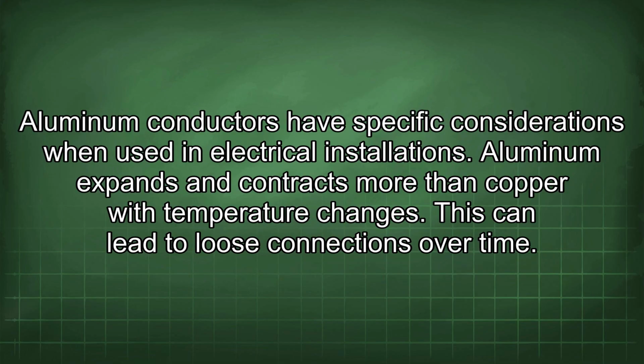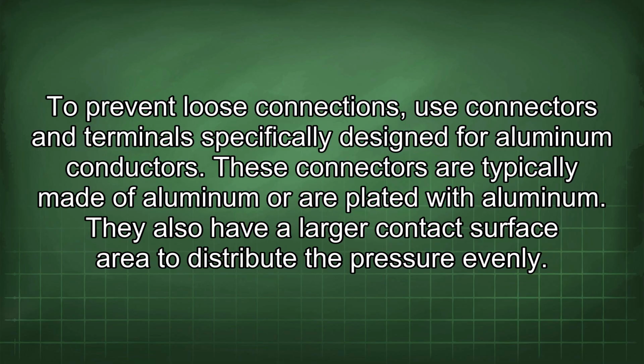Aluminum conductors have specific considerations when used in electrical installations. Aluminum expands and contracts more than copper with temperature changes. This can lead to loose connections over time. To prevent loose connections, use connectors and terminals specifically designed for aluminum conductors. These connectors are typically made of aluminum or are plated with aluminum.